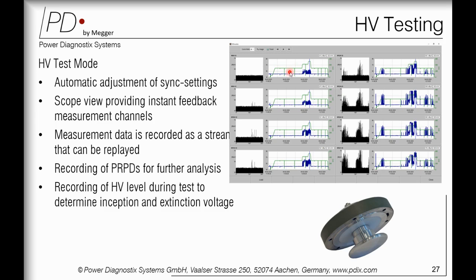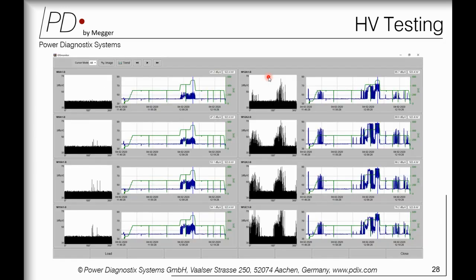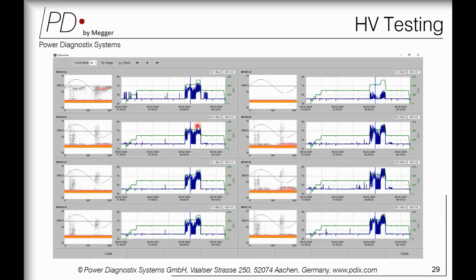It has completely automatic adjustment of sync settings. You have a scope view which instantly gets feedback from the measurement channels. It also records the PRPD pattern. You can see these are the HV modes where you have injected the voltage, and with respect to the voltage, what the PD is along with your PRPD pattern. So this complete HV testing mode is there.